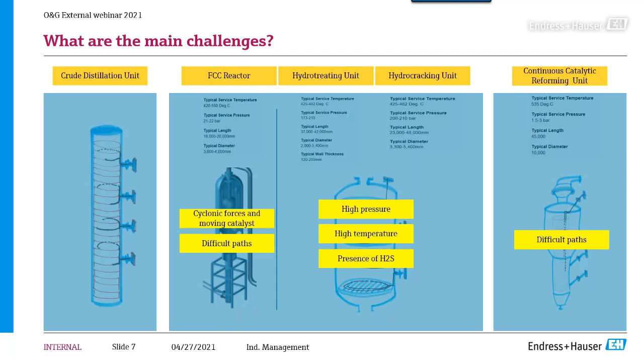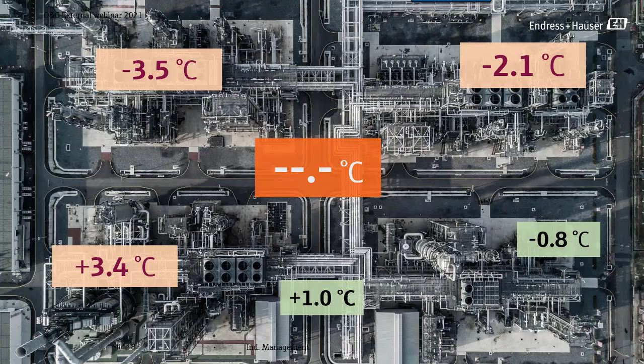In most cases, some temperature sensors, here we are talking about thermocouples, might drift because the conditions where they are measuring are very, very critical. Sometimes, or most of the cases, they drift downwards, measuring some degrees Celsius less. It also happened that they showed some degrees Celsius in a positive way, plus. But as a general rule, what I can say is that thermocouples are affected by drift or deviation over their life, and we have to keep that into consideration. I also want to explain why they do so and how we solved it.